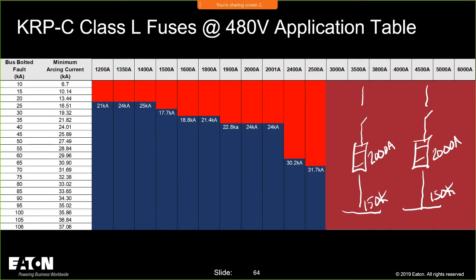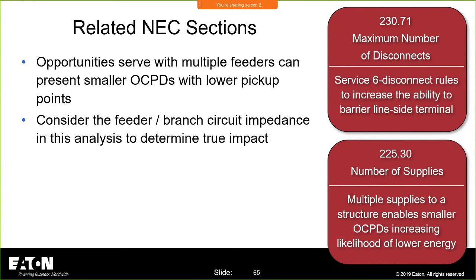But now you're using two 2,000 amp fuses instead of one 4,000 amp fuse. And I'll give you a method to say, if you wanted to keep that one 4,000 amp fuse and you apply an arc reduction technology, you're going to have to show them that the arcing current is in that region. And I'm going to show you how to do that here in a second or two. Again, there are opportunities to serve multiple feeders. We now have rules that let you do multiple feeders and numbers of supplies, so you can leverage these to take that one 4,000 and split it into two. And we talked about those yesterday.